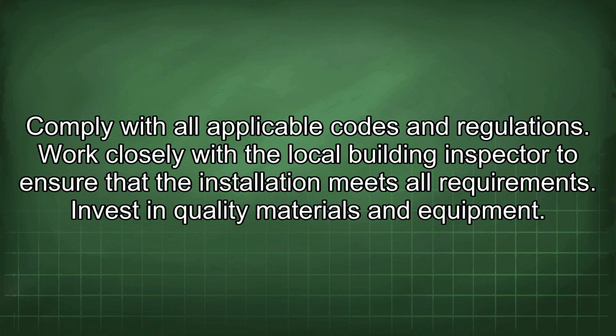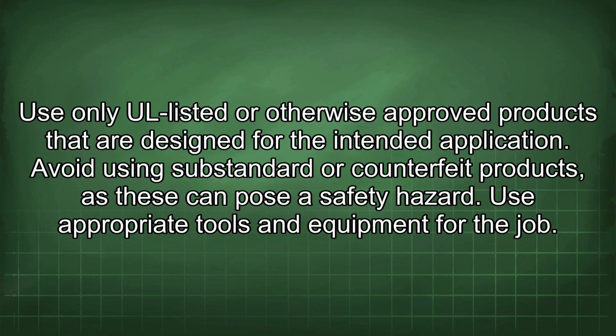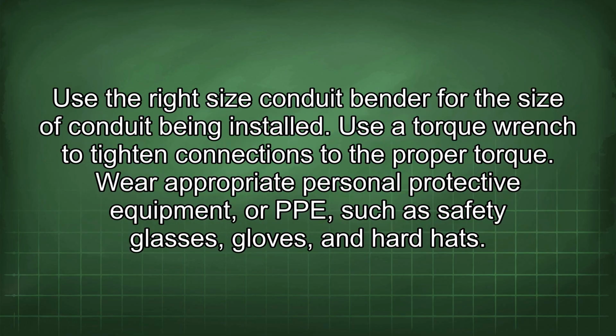Invest in quality materials and equipment. Use only UL listed or otherwise approved products that are designed for the intended application. Avoid using substandard or counterfeit products, as these can pose a safety hazard. Use appropriate tools and equipment for the job. Use the right size conduit bender for the size of conduit being installed. Use a torque wrench to tighten connections to the proper torque. Wear appropriate personal protective equipment, or PPE, such as safety glasses, gloves, and hard hats.